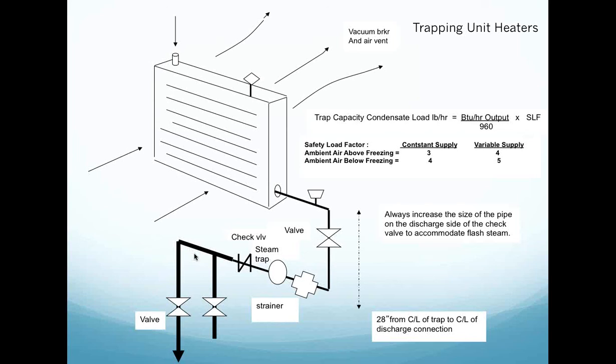And the reason I show that is because 2.31 feet, 27.7 inches, and I rounded it to 28, is 1 pound gauge, 1 PSIG. If I have a small column, whether it's 1/4 of an inch wide or 10 feet wide, at the bottom of that column, if I put a pressure gauge, it would read 1 PSIG. So what I'm trying to do is make sure that you use everything you can to help you get rid of the condensate that's formed.